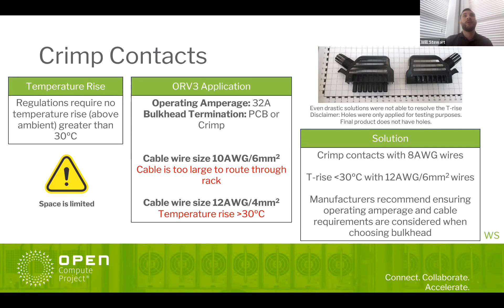As data center operators and power shelf manufacturers consider the type of power shelf and connector they're going to use, you should take into consideration the panel side connector and the termination onto the PCB, making sure everything is up to code. I think crimp contacts with 8-gauge wires is probably the best option we found for heat dissipation, and I just wanted to share that with the community.